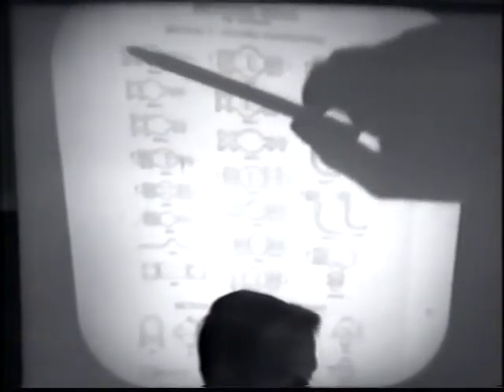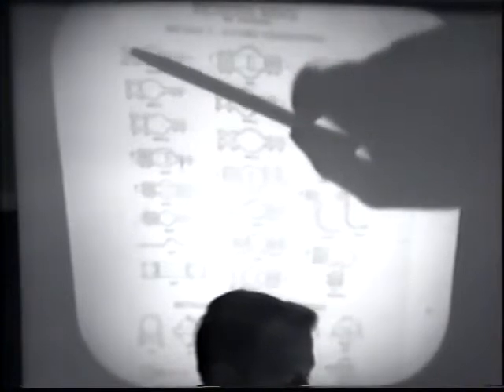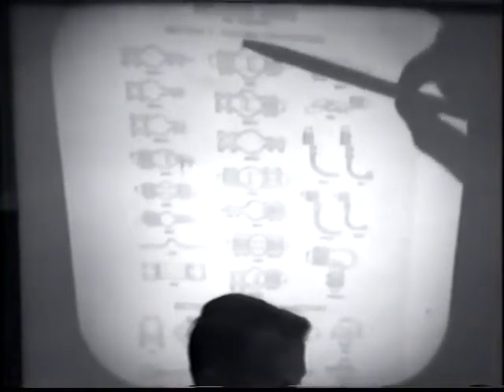These are some examples of flexible connectors that are used. You can see here we have a switch terminal that was bolted there, and these are thin sheets that allow this particular conductor here to move in and out, expand. Same thing right here. This is a tubing connector in which this part of the clamp is bolted to the tubing, and this part is bolted to the switch terminal. And this guide here allows this section of tubing to move in and out.